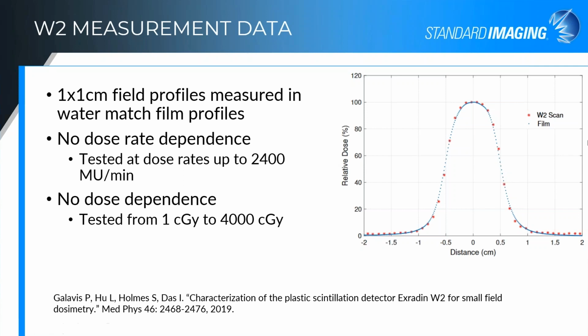So this is a comparison of film and W2 measurements for a 1x1 field, 1 centimeter field profile scan in a water tank. They also investigated dose rate dependence and dose dependence, and just as with the W1, those dose rates up to the FFF beams that were tested, as well as dose linearity from 1 centigray to 4,000 centigray. There wasn't any dependencies seen there.